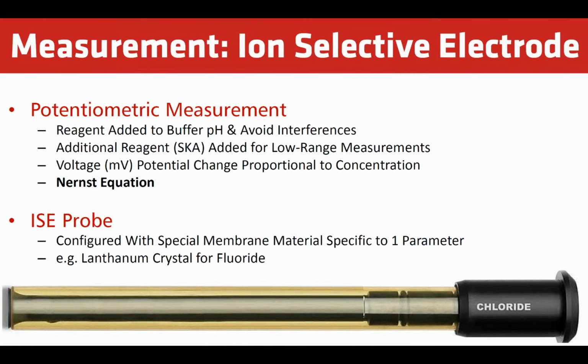Here we're taking a look at what we call ion selective electrode measurement. These are either a pH probe or an ISE probe used with various buffers and standard known addition for ISE for low range. So we actually spike the sample with a known amount. So in this case, let's talk chloride. That's a chloride probe.